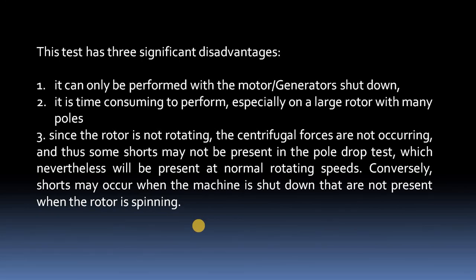Despite its disadvantages, the pole drop test is very simple and easy to perform — we only need a variac and a multimeter. However, as far as identifying shorted turns is concerned, the RFM method — the Rotor Flux Monitoring online technique — is very useful and reliable. We will see that in the next video. Thank you so much.